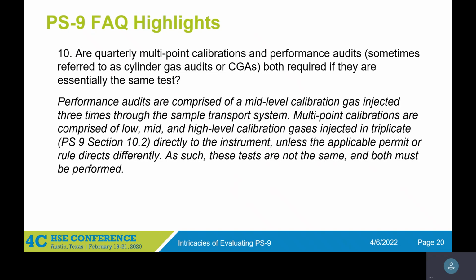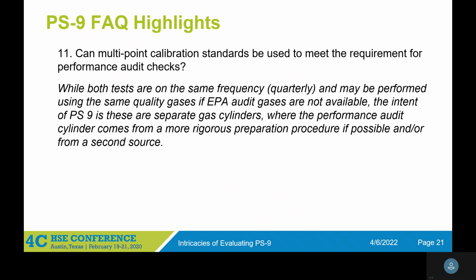This is another interpretation area where I've seen people take their full multi-point PS9 results and flow those through the sample system so that they could use the mid-level as part of their performance audit. But that depends on your interpretation of this and the next question even more so, because it's a question on the calibration standards: can the multi-point calibration standards be used to meet the requirements for performance audit checks? And this spells out that the intent was that the performance audit cylinder was a more rigorous gas procedure, if possible, or from a second source.